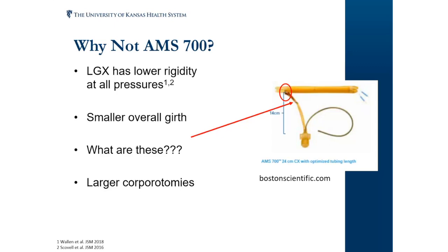I jokingly have this arrow pointing to what are these? These are the Gore-Tex sleeves that cover the tubing. These are put on because of manufacturing issues with the actual device. If that tubing is put in continuity with the actual cylinder for long periods of time, depending on temperature changes, it can actually cause it to bind to and then tear off the cylinder and ruin that outer silicone layer. So these are there to protect the implant and can be removed during surgery.